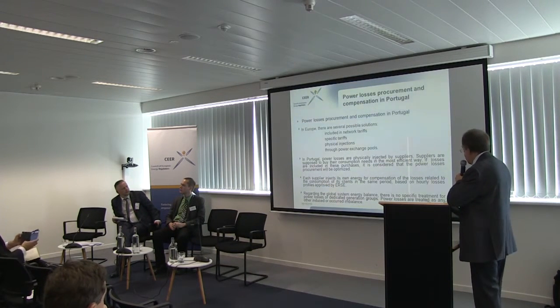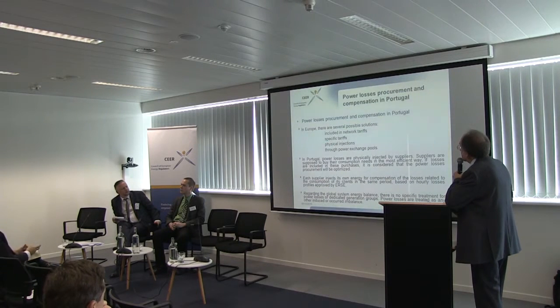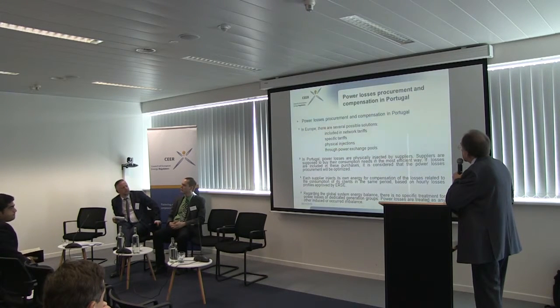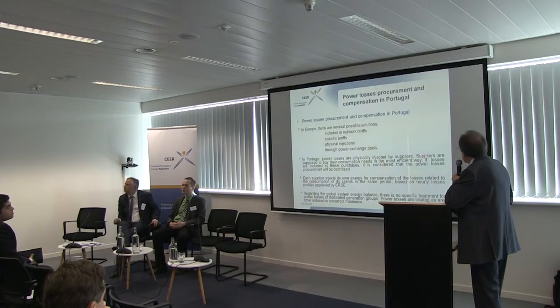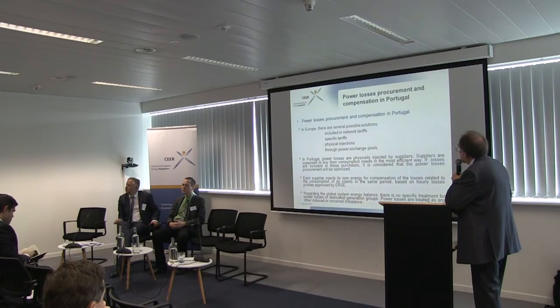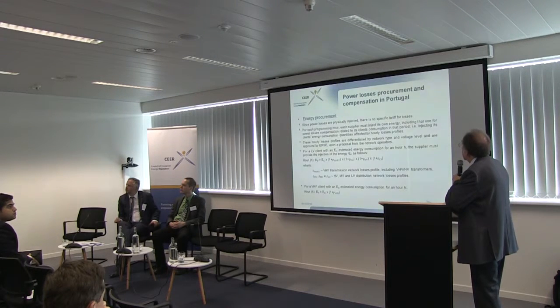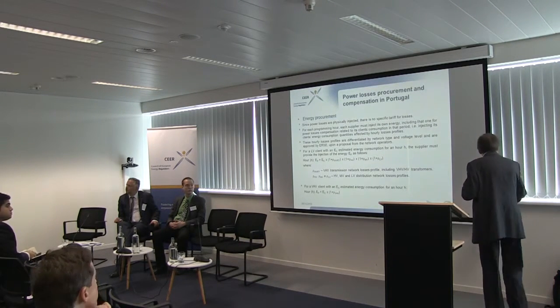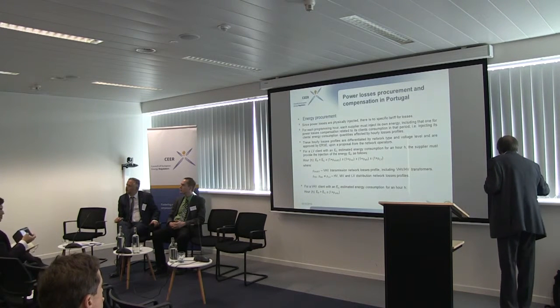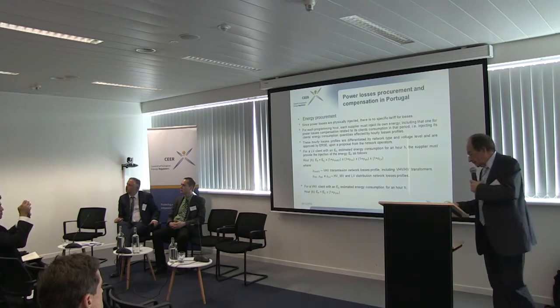In Portugal, we have physical injections. So for each programming hour, suppliers must inject into the system the energy for losses related to their portfolio. There is a specific treatment for losses at each voltage level. Power losses are considered as any other imbalance on the system — there is no dedicated tariff for losses in this model.